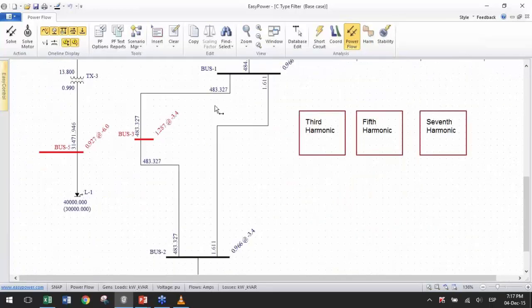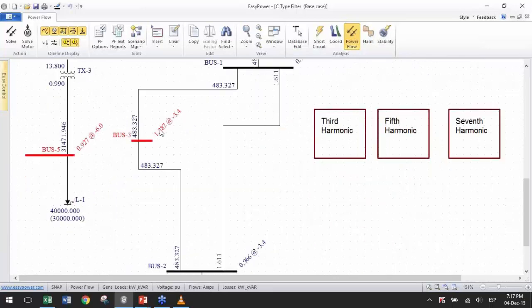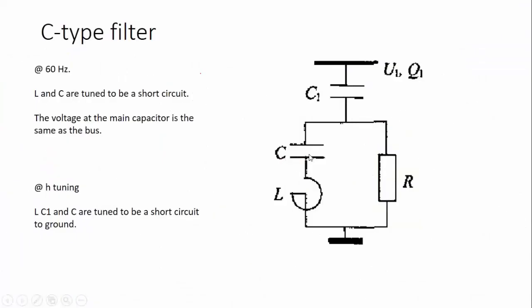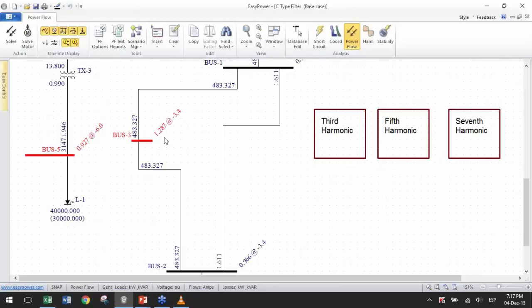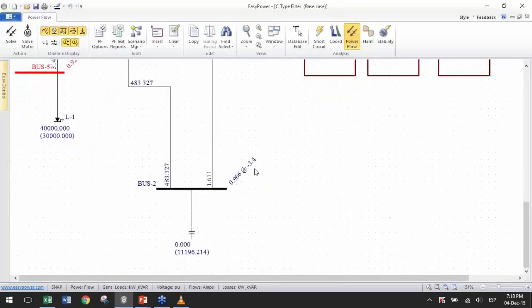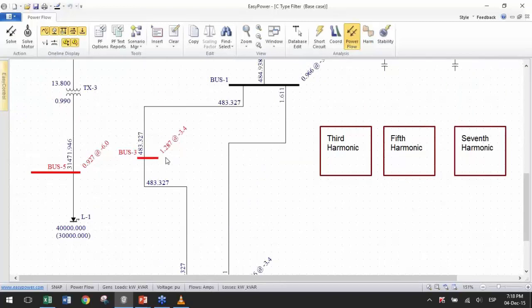Now, another important thing is that this branch is acting pretty much like a notch filter. So the voltage for the capacitor, remember, this branch, this one in here, is a model of this capacitor. And check it out, the voltage is a little bit higher. So when you're designing your filter, you should take that into consideration. The capacitors for the tuning branch will have a fairly larger voltage depending on the harmonic, but it will be much higher than the power capacitor, which is not even at 1 pu. This one is at almost 1.3 pu. You should watch out for that. So much of the current is going through here. What about the power?